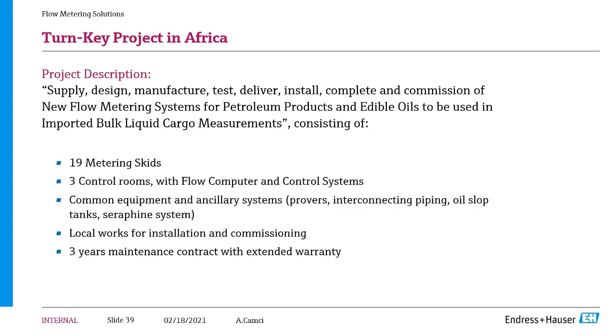The project scope was 19 metering skids in 3 different harbors. These 3 harbors have 3 control room shelters installed with flow computers and control systems, the MCC and such. The systems have all the common equipment and ancillaries like provers, interconnecting piping, oil slop tanks, and so on. All the local works for installation and commissioning were done by the Endress+Hauser team, and we also have a 3-year maintenance contract and extended warranty on the system.